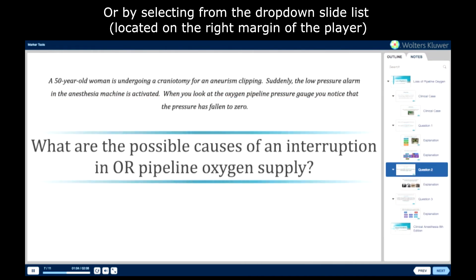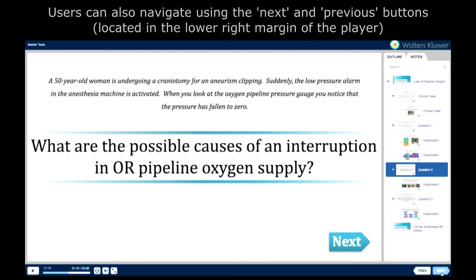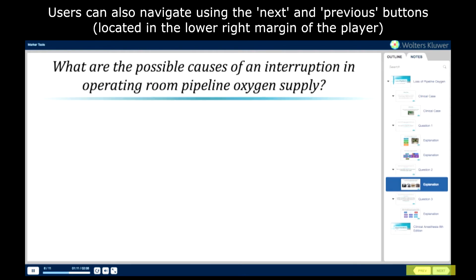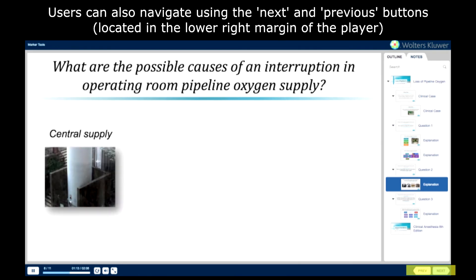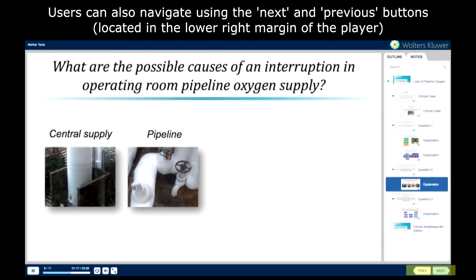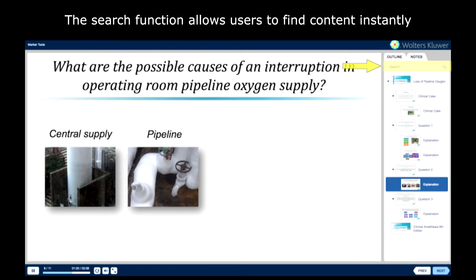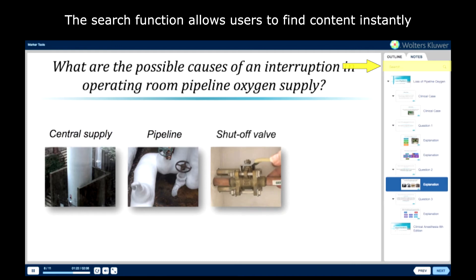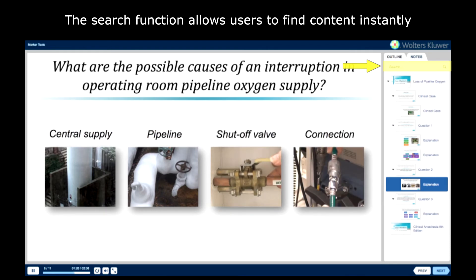What are the possible causes of an interruption in operating room pipeline oxygen supply? There are a variety of possibilities, including depletion of the hospital's oxygen central supply, and disruption of the pipeline from the central supply to the operating room. It is also possible for the operating room shut-off valve to be turned off, or for failure of the connection from the anesthesia machine to the wall outlet.